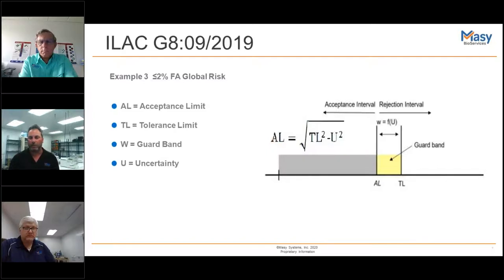What this is saying is that there's a 98% accuracy to your measurement, so we make a statement of conformity: pass, fail, in tolerance, out of tolerance. Just like uncertainties themselves, K equals 2 is 95% confidence, and that's not 100% - nothing is 100%. So this is a risk analysis that will take the measurement, the tolerance, and the uncertainty and come out with an acceptance limit.